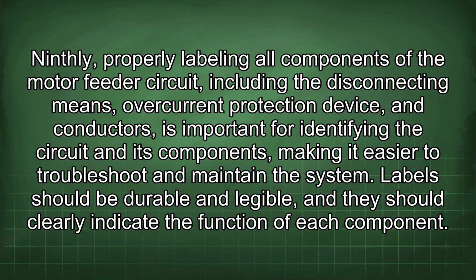Ninthly, properly labeling all components of the motor feeder circuit, including the disconnecting means, overcurrent protection device, and conductors, is important for identifying the circuit and its components, making it easier to troubleshoot and maintain the system. Labels should be durable and legible, and they should clearly indicate the function of each component.